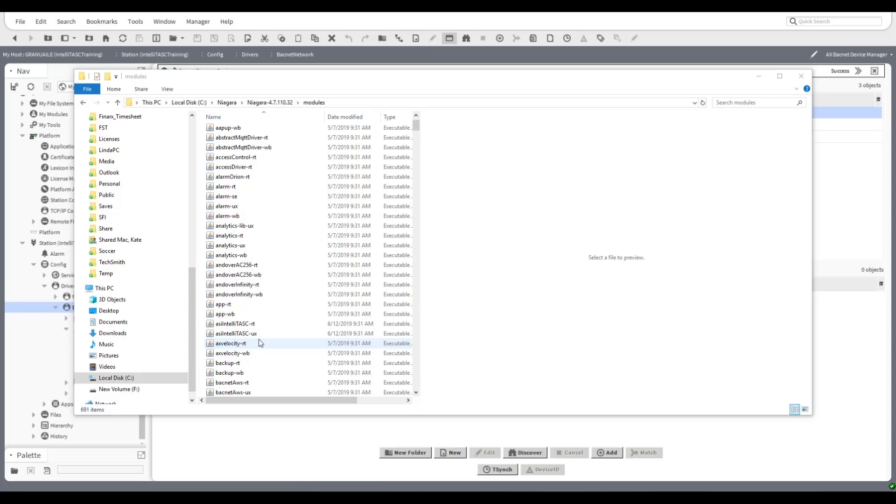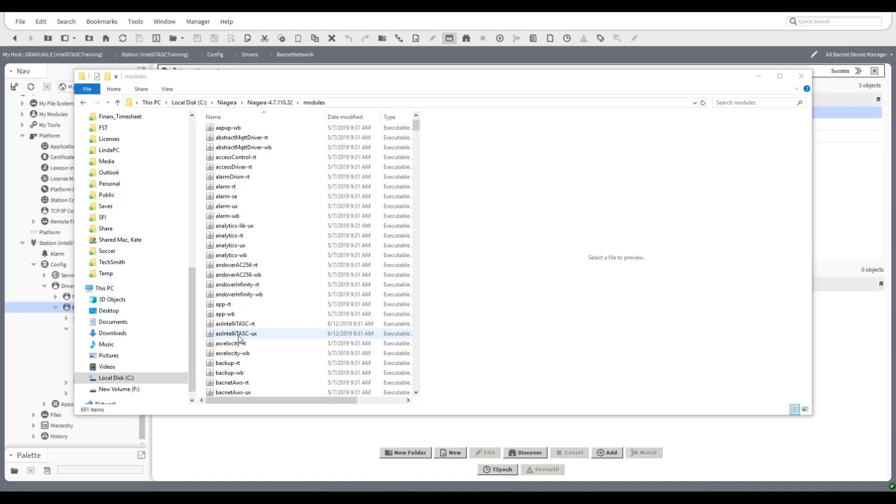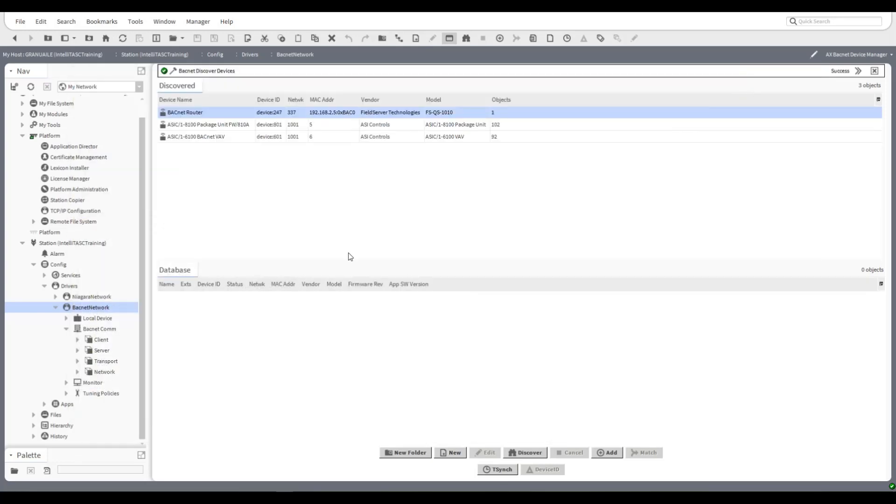These need to be loaded as usual into the Tridium Niagara modules folder, and if you've worked with other modules you'll know once you've loaded these you are going to have to reboot your workbench and your JACE if you're loading these onto a JACE. Please make sure this gets done before you get started with the next step which will be to have a look at the system inside of your station.